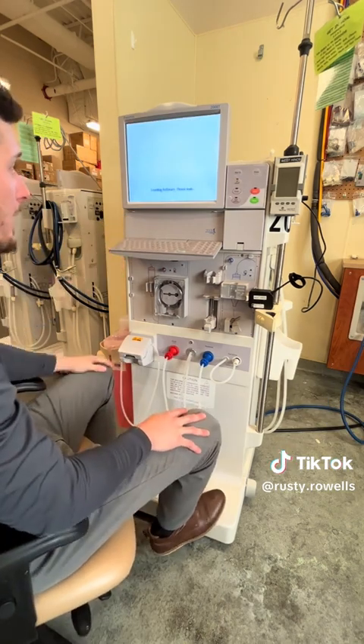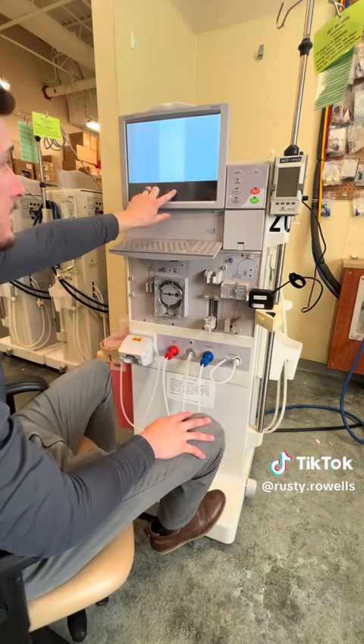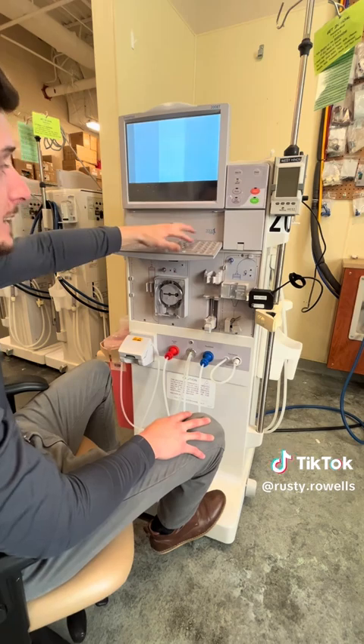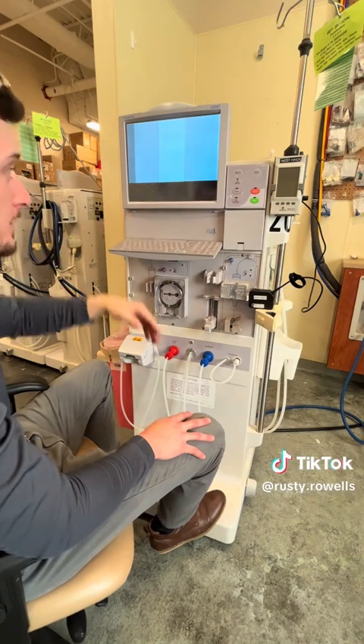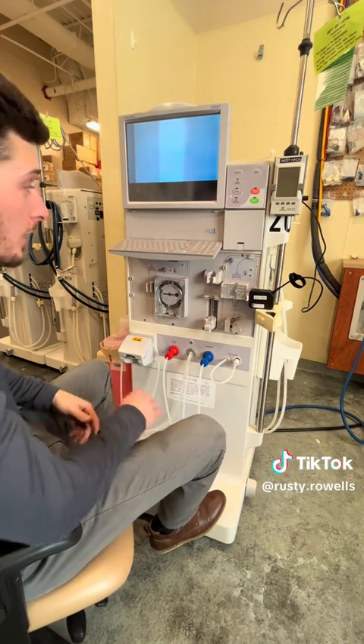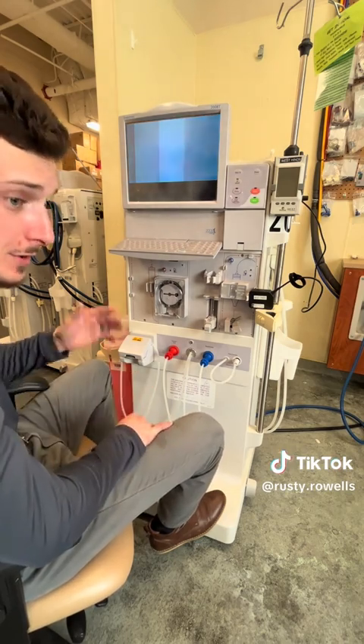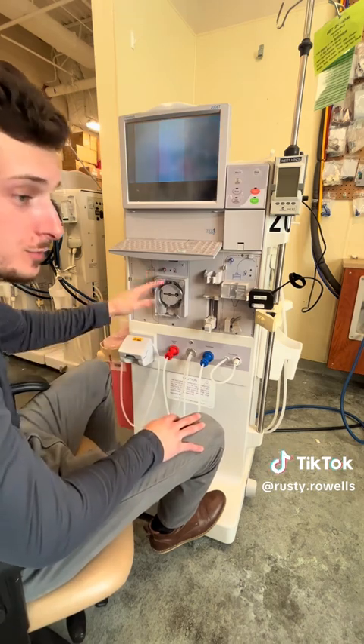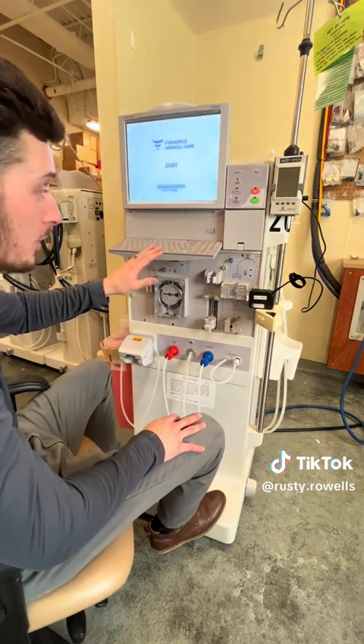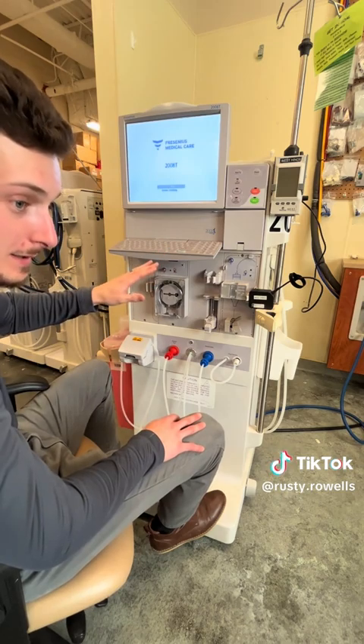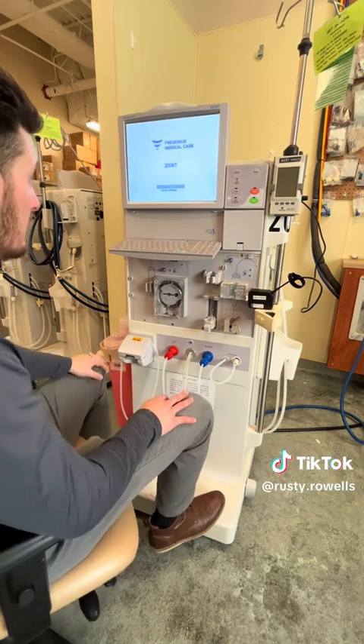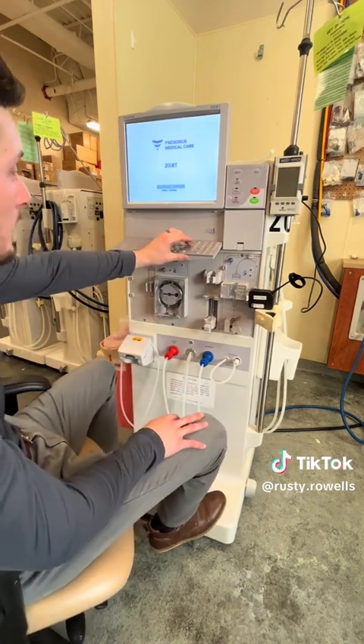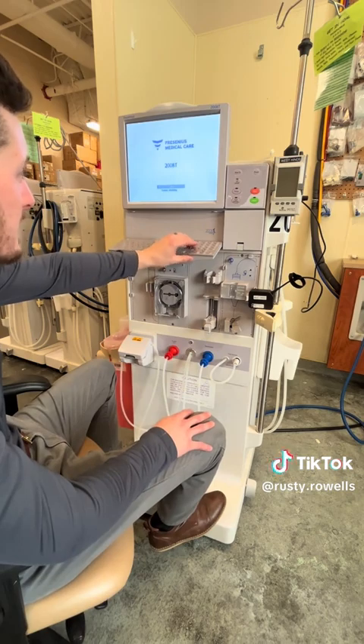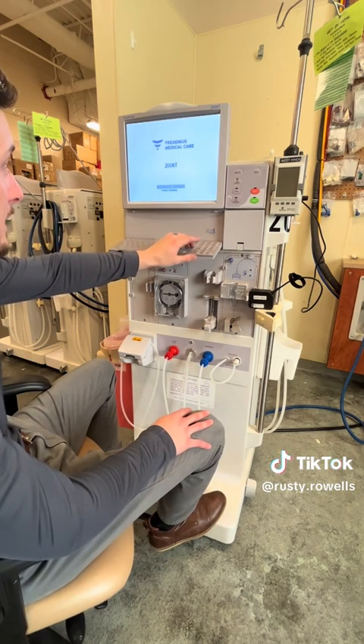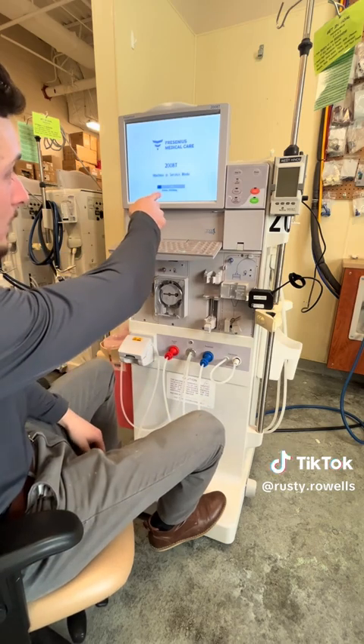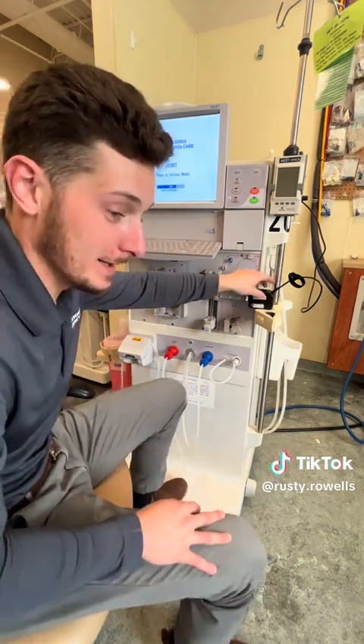Turning the machine on now, and we are waiting for our window to hit the enter button. This is how you get into service mode. If you are a tech or a nurse out on the floor, you do not need to go into service mode for anything. Let me be very clear about that. So you get to 2%, we're kind of waiting for that 11%, and then we start hitting enter. And now we're in service mode. We're going to go ahead and get everything set up.